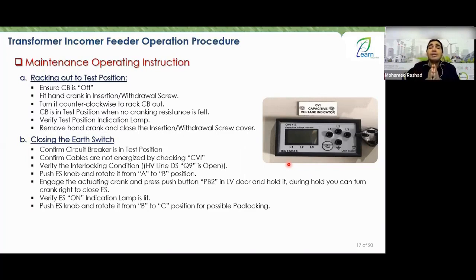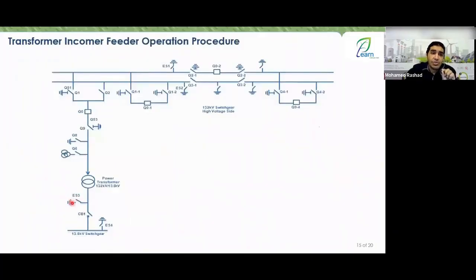Last time, to close the grounding, your interlock was to open the breaker and wait 10 minutes for the charge to discharge. This time, you don't have a capacitor bank. What do you have? You have a transformer. So how do you handle it? They told you to go here, the grounding you want to close. You must ensure that Q9 above is what? Q9 above must be open, exactly.